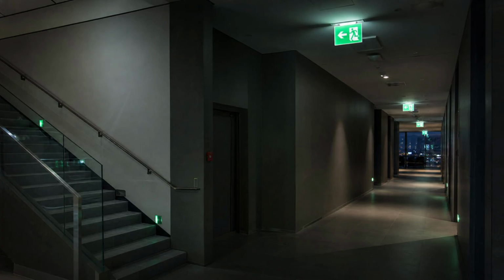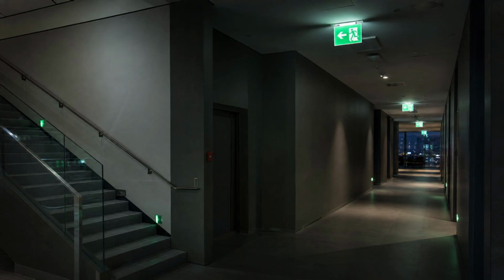And all of it is held tonight by people who planned it and installed it and test it and maintain it. Engineers who spent careful hours designing the separation of circuits and the sizing of generators and the arrangement of transfer switches. Technicians who climb into generator rooms on scheduled maintenance days and check the oil and test the batteries and sample the fuel and record the results in logs that will tell the truth about whether the system is ready. Facilities managers who review those logs and order replacement batteries when the capacity tests show diminishing returns and arrange fuel deliveries before the tank drops too low.